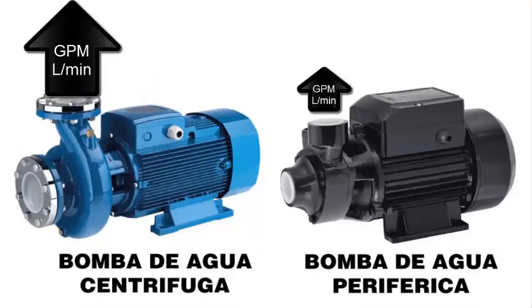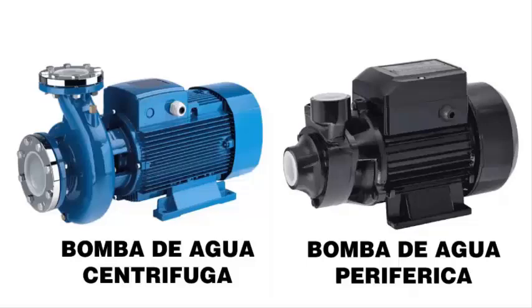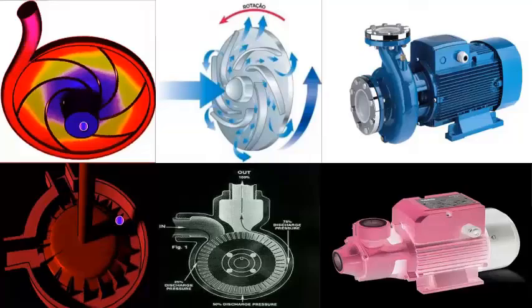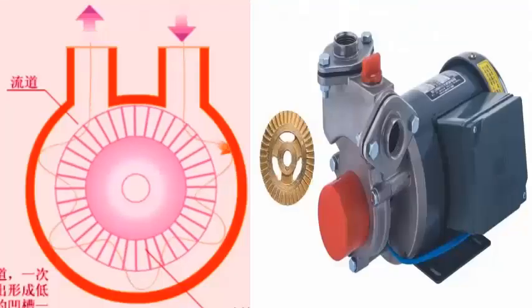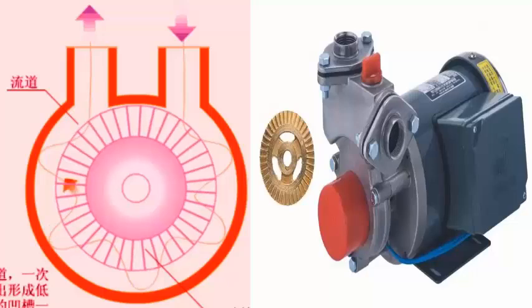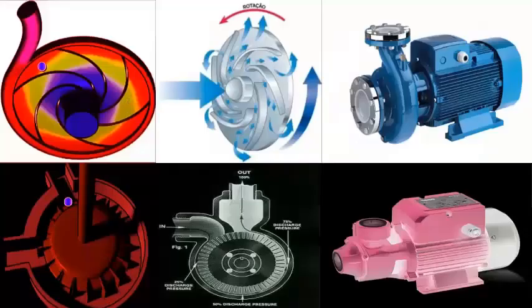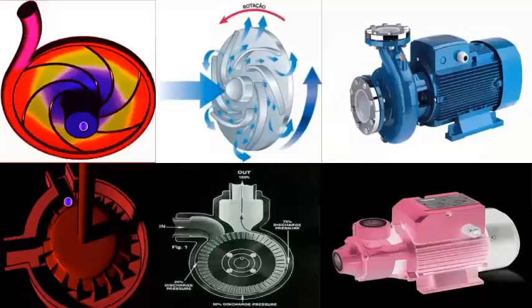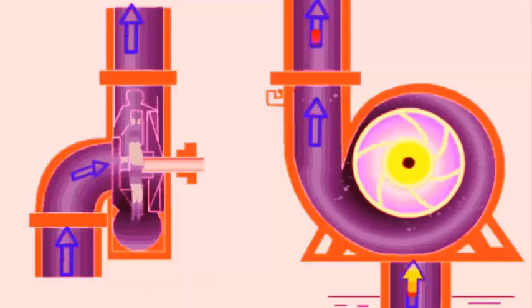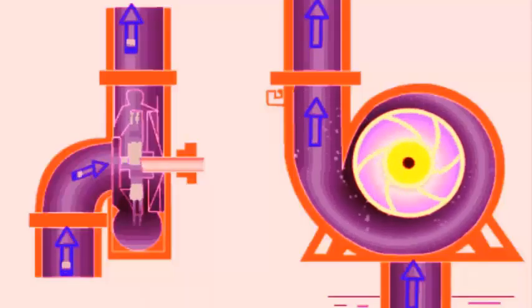2. Fluid Path. In peripheral pumps, the fluid follows a longer and more turbulent path due to recirculation, increasing accumulated pressure. On the other hand, centrifugal pumps are designed to move the fluid quickly toward the outlet, making them ideal for applications requiring higher flow rates without recirculation.